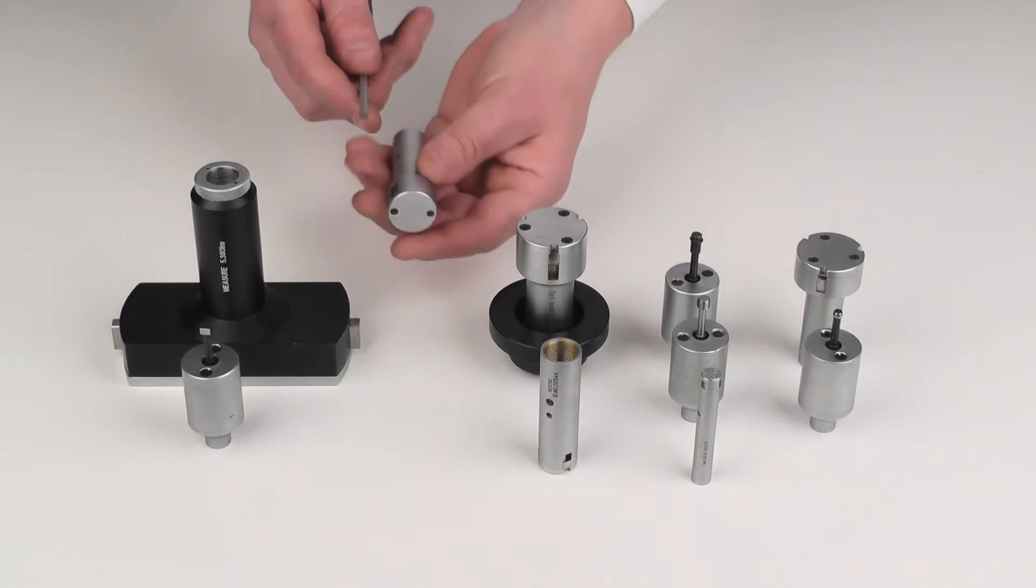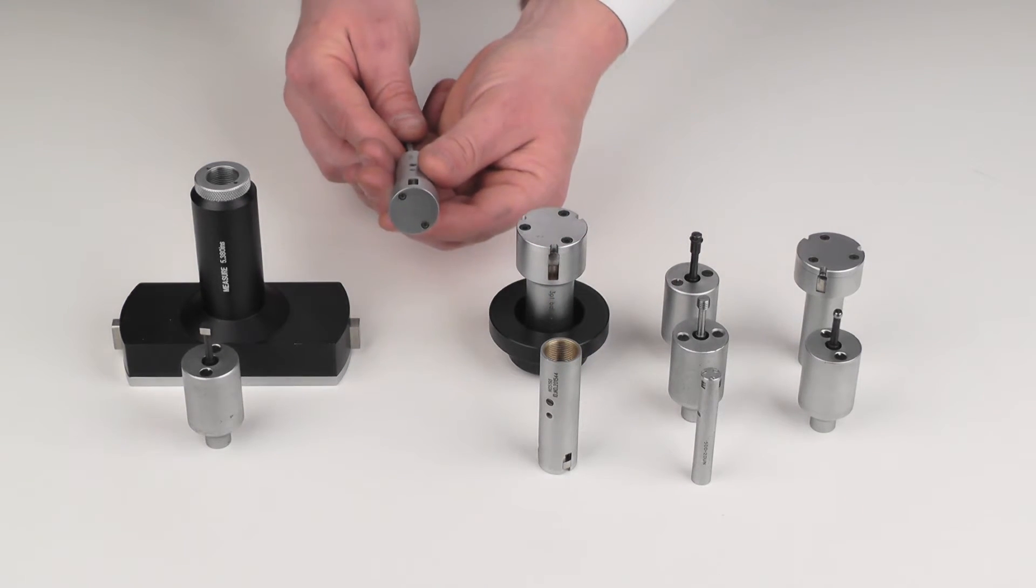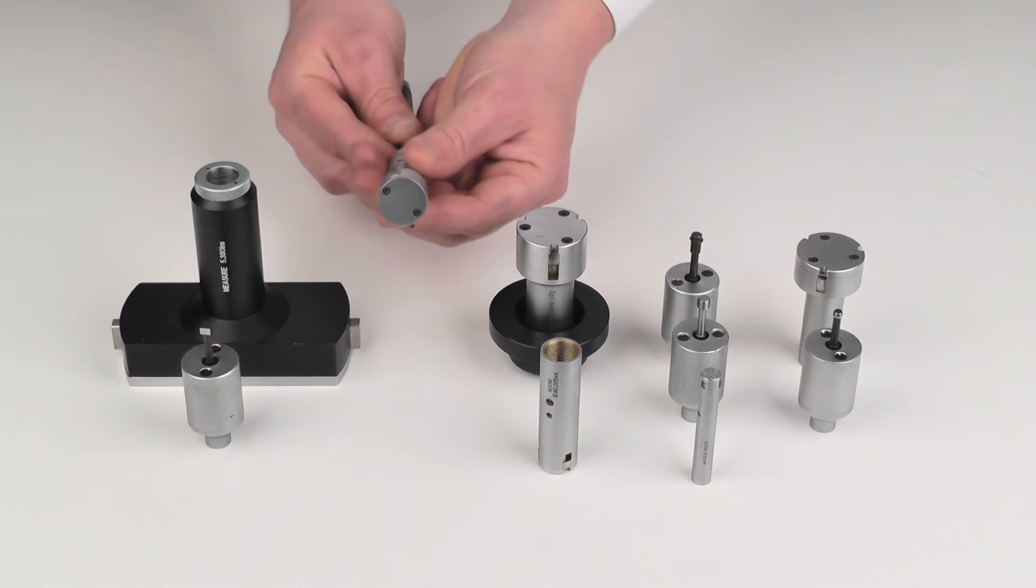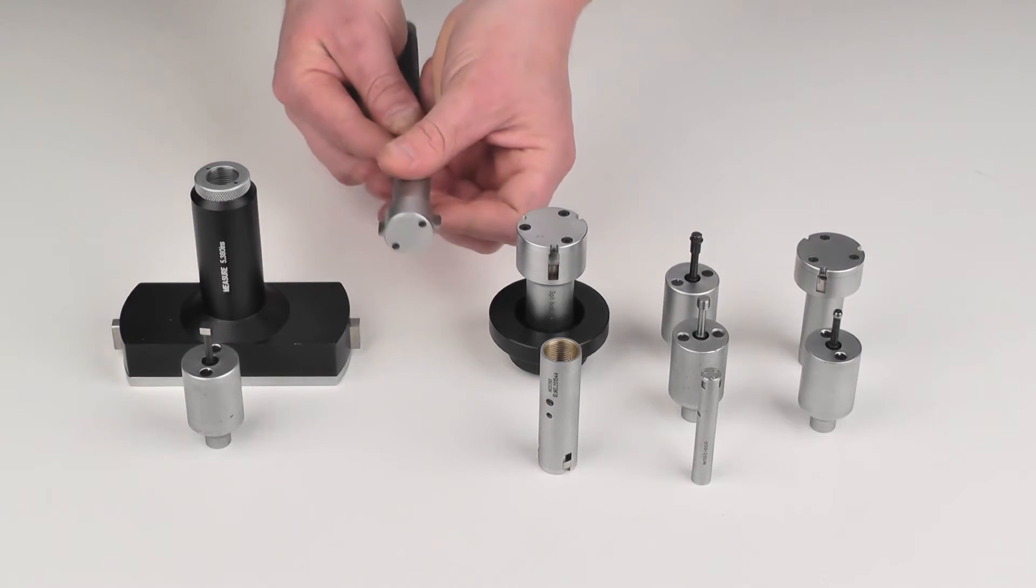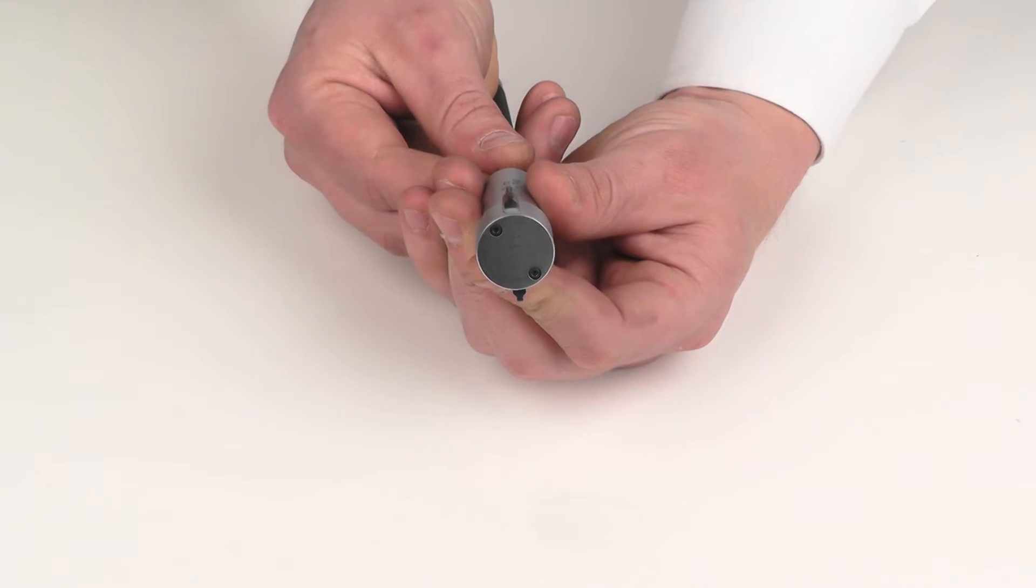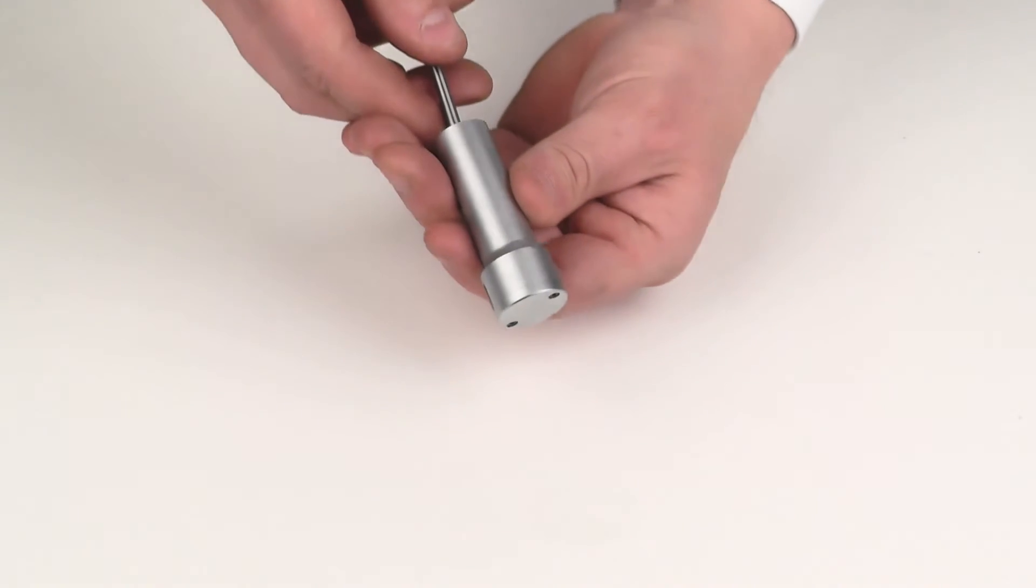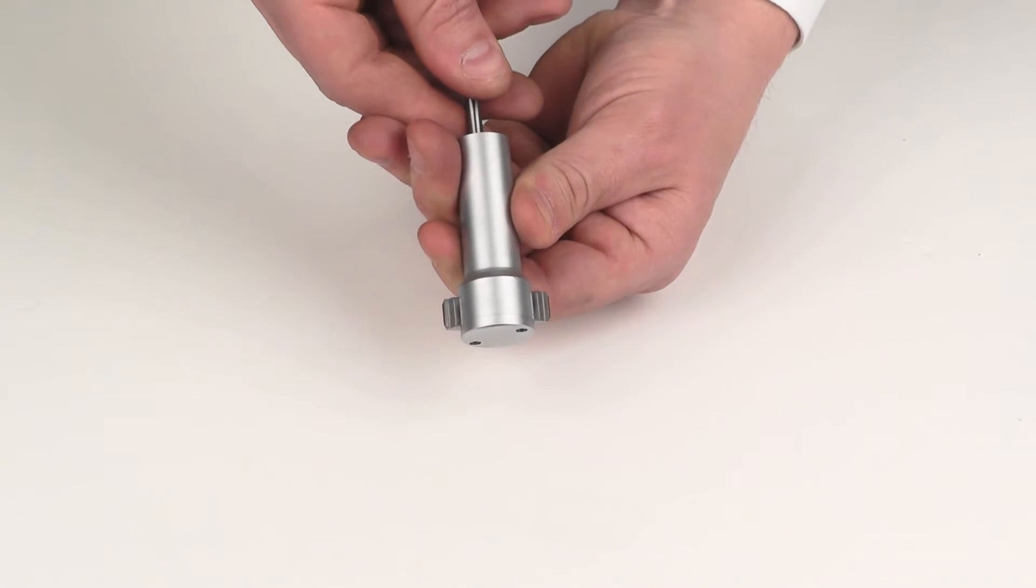For between measurements for drive splines or between pin measurements, we have a two-point system where the pin diameter is actually built right into the anvil. These are one-piece anvils, very tough.